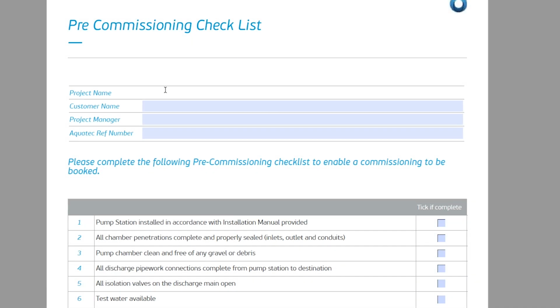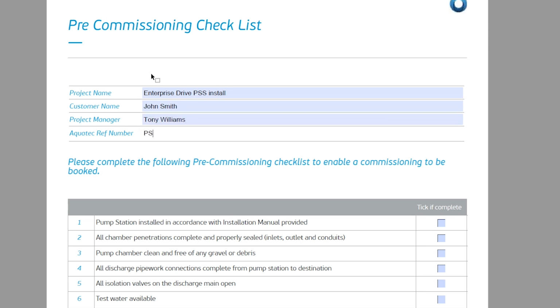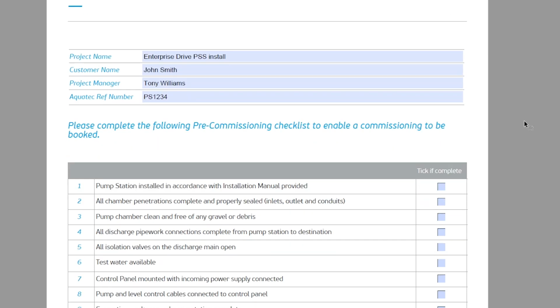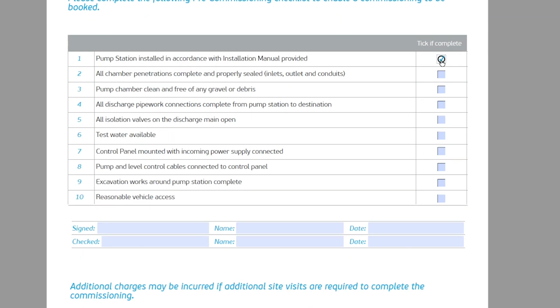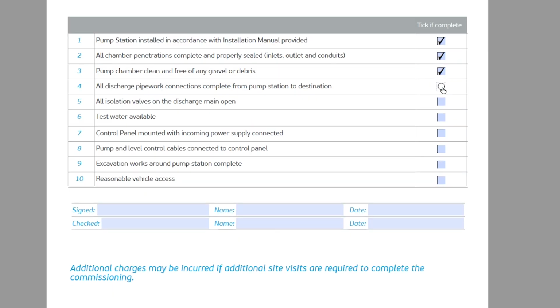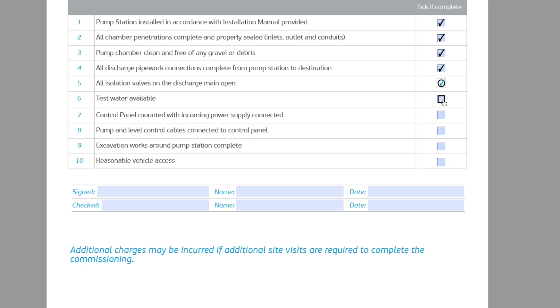Page 1. Verify the pre-commissioning checklist has been completed by the client or installation contractor. This checklist needs to be signed and provided to the commissioning agent prior to booking in the job date for the commissioning. The purpose of the pre-commissioning checklist is to confirm that all electrical and plumbing connections are complete, test water is available, and the site has safe access, allowing the commissioning to proceed.